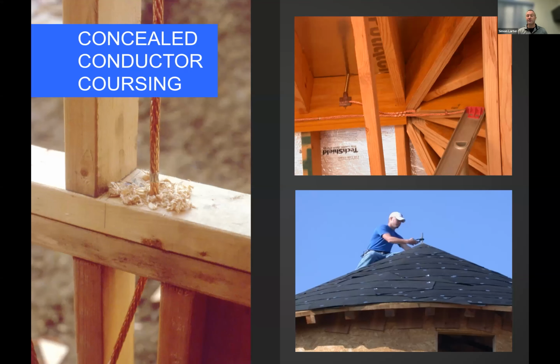Concealed conductor coursing, yes. A lot of the time we do conceal our conductor within a building. It happens a lot in residences when we're doing a system during construction. The main thing about that is, yes, we are fastening that lightning protection conductor directly to the wood. It doesn't heat up appreciably in a lightning storm. If lightning gets on that cabling, it's through and done before that conductor can heat up at all. So it's no danger to the wood, even though just as a matter of housekeeping, I would probably get rid of those wood shavings on the left-hand side. That's not going to look good.